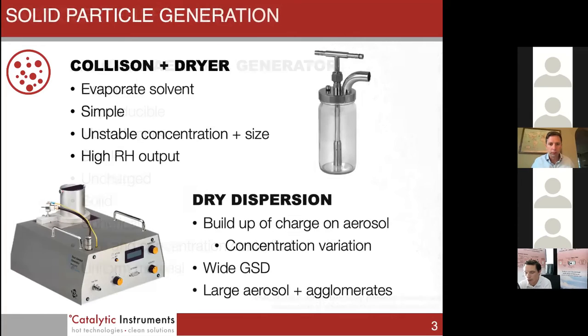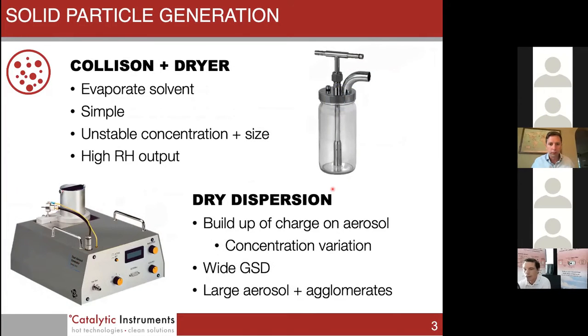There are reasons why that would make a good aerosol for testing. For solid particle generation, we have Collison nebulizers where you can evaporate the solvent. They're simple and readily available, but the issue is that they're somewhat unstable in concentration and size with high RH output. They're quick and dirty, but there are challenges with these. Then we have dry dispersion, for example this TSI generator which has high buildup of charge on the aerosol and some concentration variation. There's typically a wide GSD and the aerosol is often large and suffers from agglomerates.